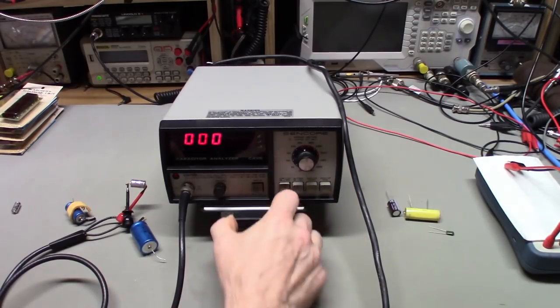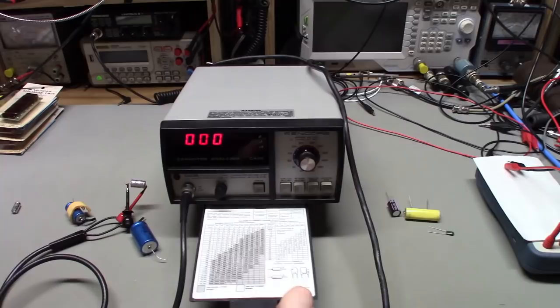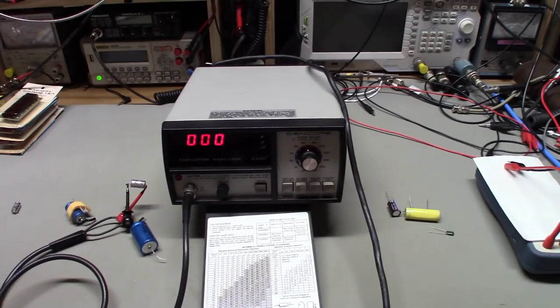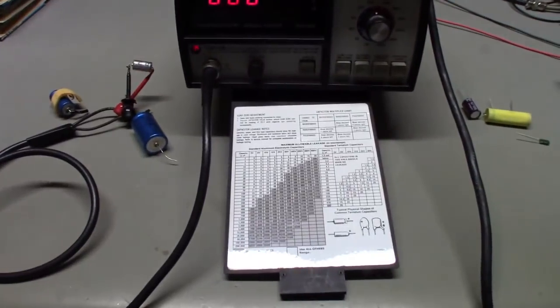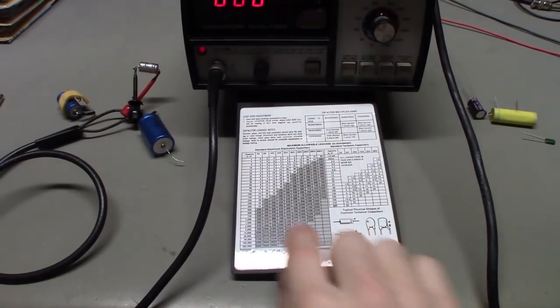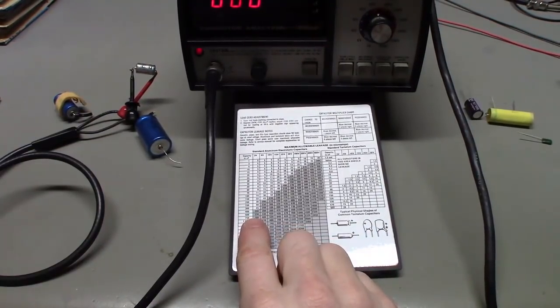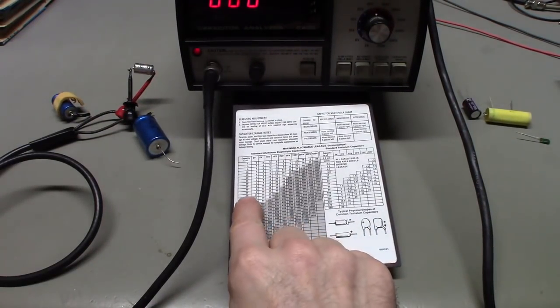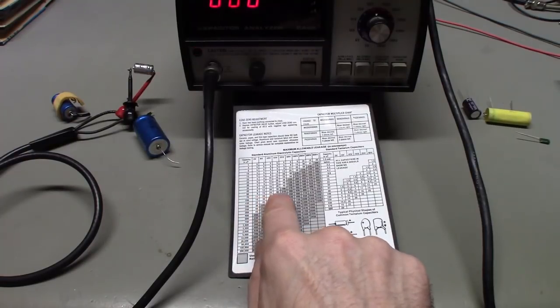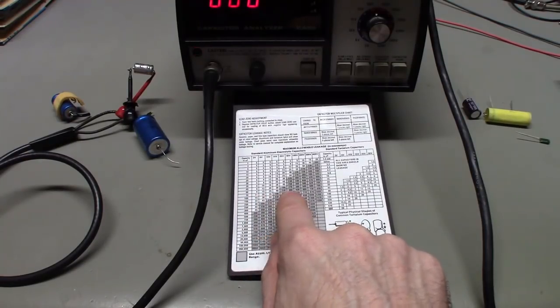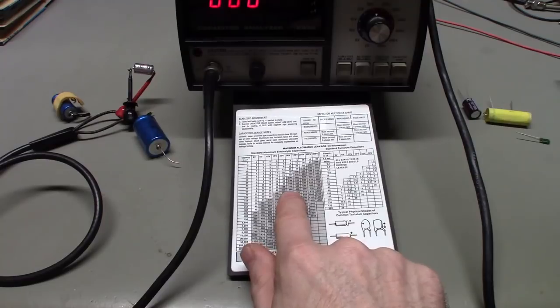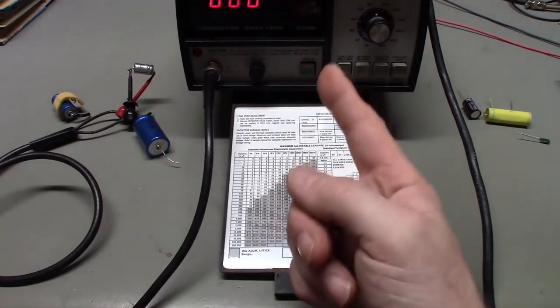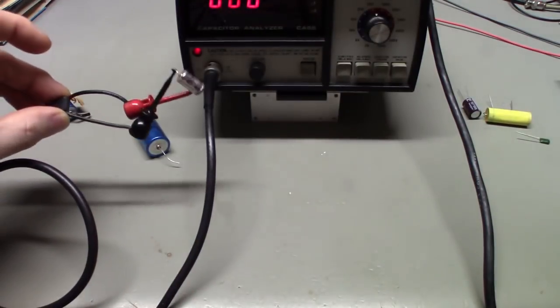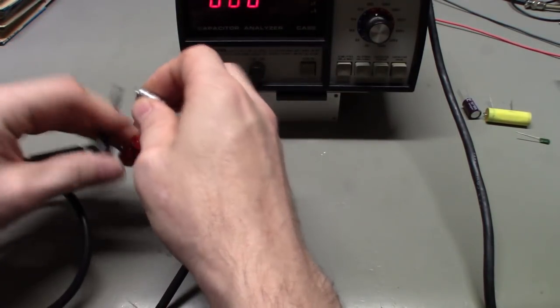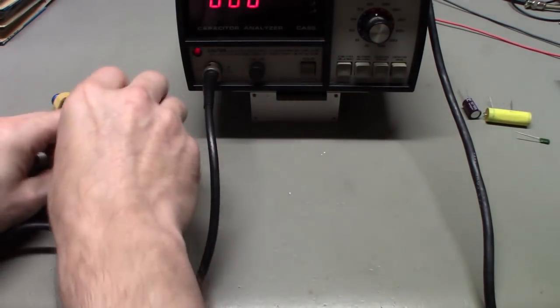And there's a little chart. As I said, all Sencore equipment seems to have these little handy pull-out charts, which is nice because that way you don't lose it. So that capacitor's 50 microfarads at 50 volts. If we look at 50 and then come over to 50, we can see the maximum allowable leakage current is 300 microamps. This one was showing 10 microamps, so that capacitor is still fine. There's really nothing wrong with it. Like I say, still going to change it. I'm not going to take a chance.